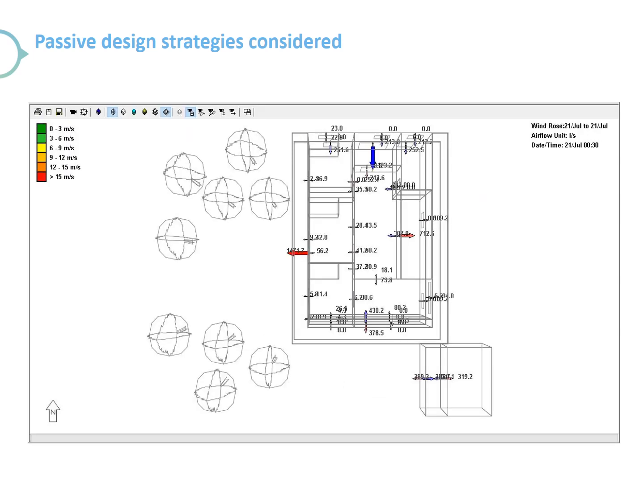This macro flow diagram shows the wind direction or the airflow inside the building in summer, July 21. We can see in this diagram that the cold air is coming from outside and the hot air is going outside, which is a great result for airflow. And also we can see that the Trombe wall is doing a great job of sending the hot air outside and getting the cold air inside.